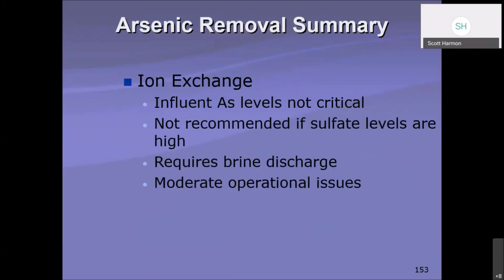Ion exchange influent arsenic levels in this particular case are not critical. Not recommended if sulfate levels are high. Again, it'll bind with your resin in your ion exchange. Requires that brine discharge, which may definitely require some type of permit because of the hazardousness of that. There's some moderate operational issues with that, simply because it's a little more complicated.